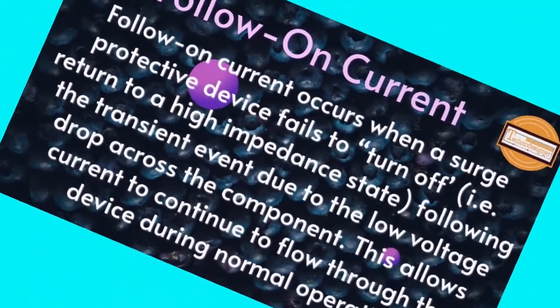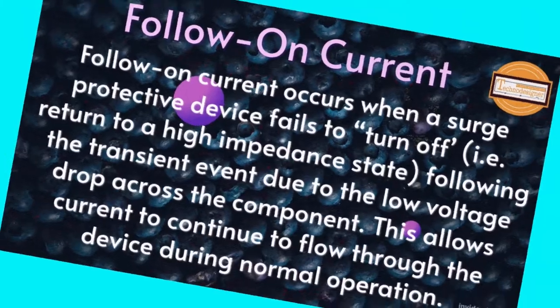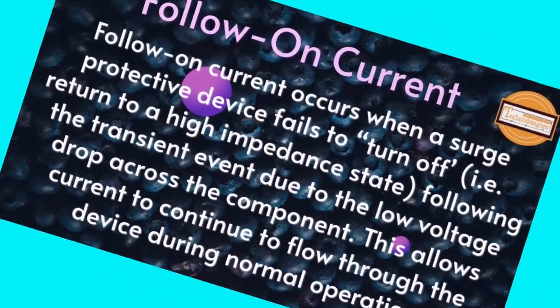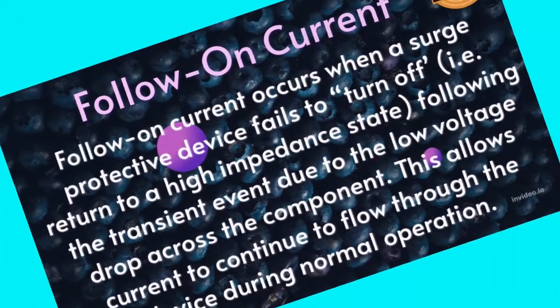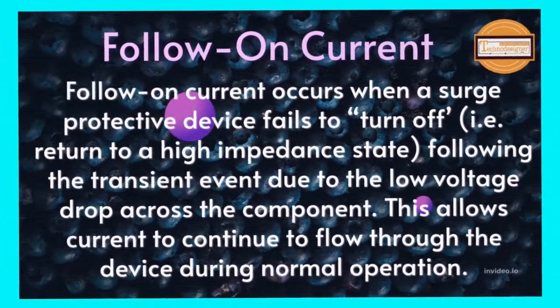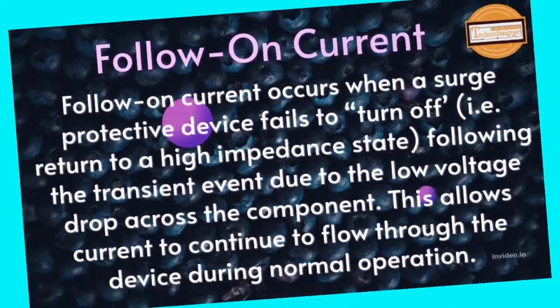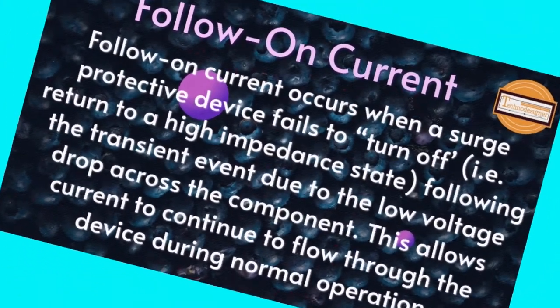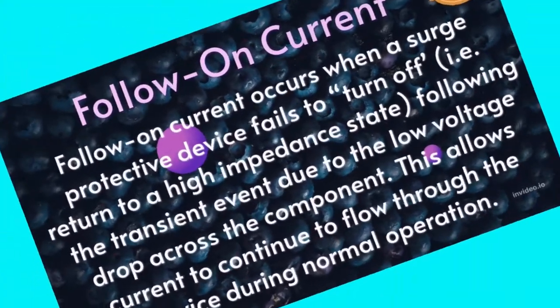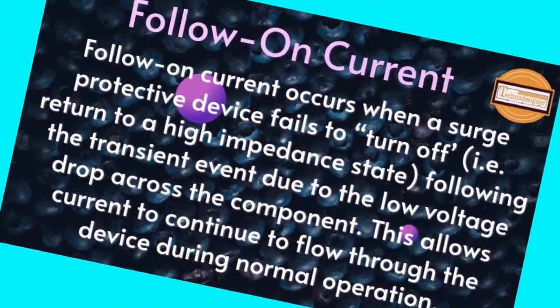Follow-on current occurs when a surge protective device fails to turn off, i.e. return to a high impedance state, following the transient event due to the low voltage drop across the component. This allows current to continue to flow through the device during normal operation.